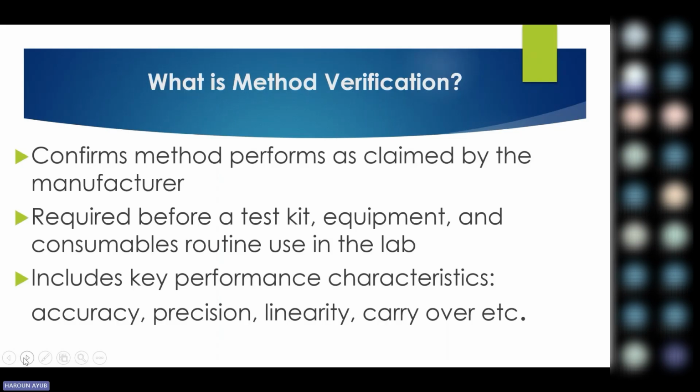Unless there is an emergency where you really have to run that particular patient, you have to do that particular background test at least 3 times to ensure that all remnants that might be remaining are cleared, because if you check your manual, not all materials have a 0% carryover rate. There's some percentage that the manufacturer has studied, and it's there. So you find that those particular instructions form a key part. That's the same thing that we are saying when you're doing carryover studies.